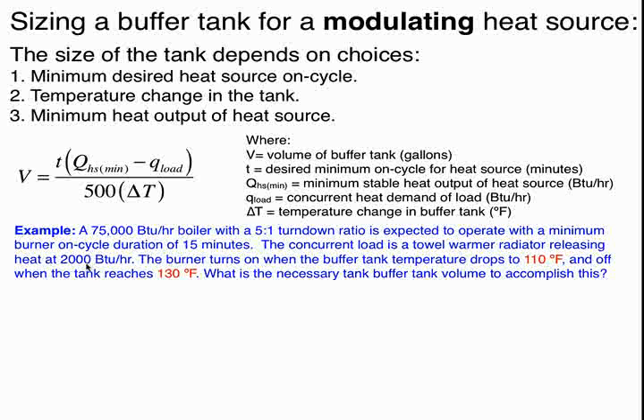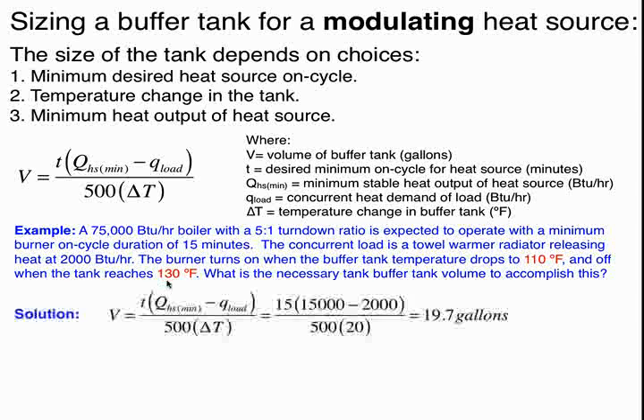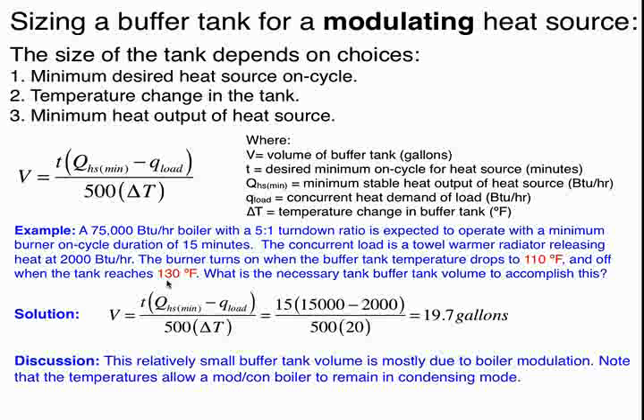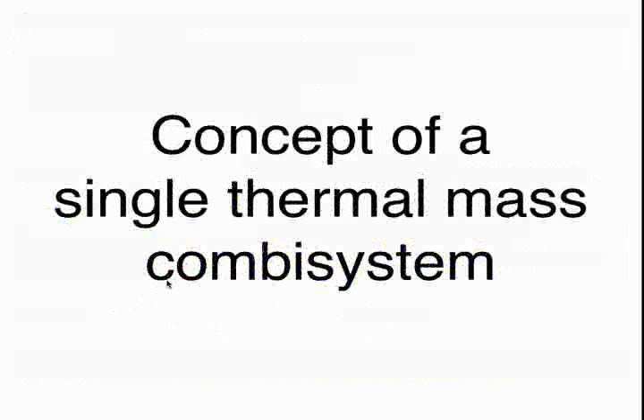We're going to shoot for a minimum burner on cycle of 15 minutes. We're going to assume that our towel warmer releases 2,000 BTUs per hour. And I'm purposely putting in a narrower delta T here. We're going to start that burner when we drop down to 110 in the buffer tank. We're going to turn it off when we get up to 130, so we only have a 20-degree swing. Put the numbers in the formula, and you can see it's about a 20-gallon tank. So again, there are applications where smaller buffer tanks make sense, and a modulating boiler in a small residential application is a good example of that.